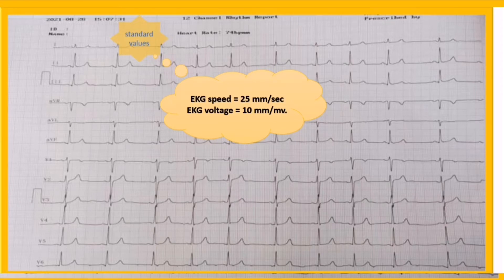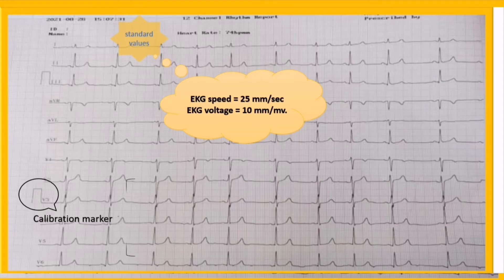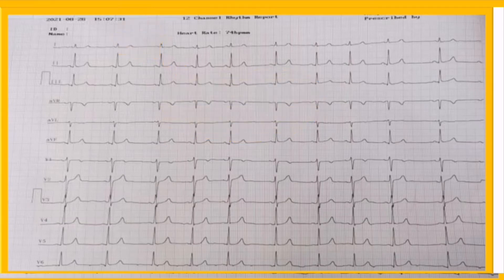Using the calibration marker is a better and faster way to check standard values. We expect the calibration marker to be two large boxes tall and one large box wide. As you see, the calibration marker here is standard, so this is a standard and acceptable strip.